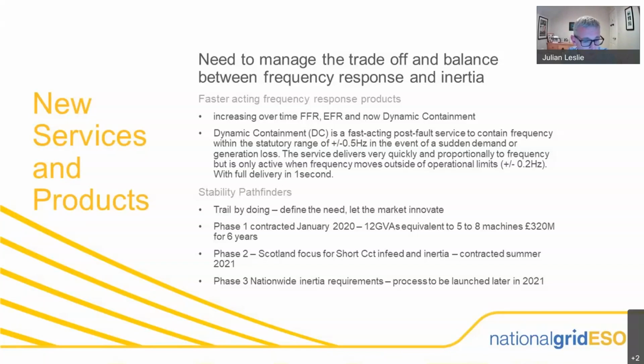GE purpose-built machines, and their sole purpose was to meet the needs of this contract. These are quite compact rotating machines, and they are as heavy as you could possibly make them. Each one weighs 200 tons, and they rotate and synchronize with the grid, and they sit there 24/7, 365, providing short circuit infeed and inertia. It's taken us 18 months to get from contract award to the machines on site, and the final one of those 2 machines was commissioned last Friday. So in phase one we bought 12 GVA seconds. As I said earlier, we need about 130 overall on the grid system. So that's nearly 10%, but that's 5 to 8 machines equivalent, gas units or coal units.